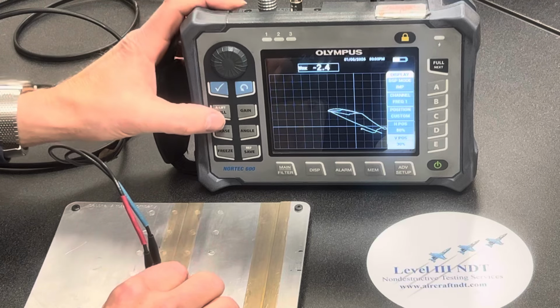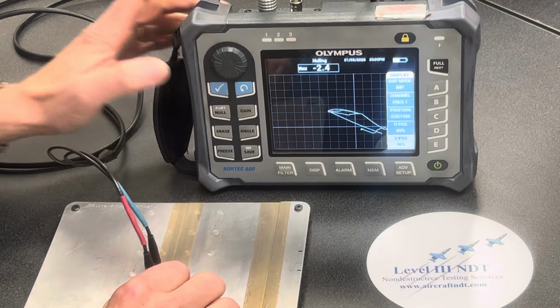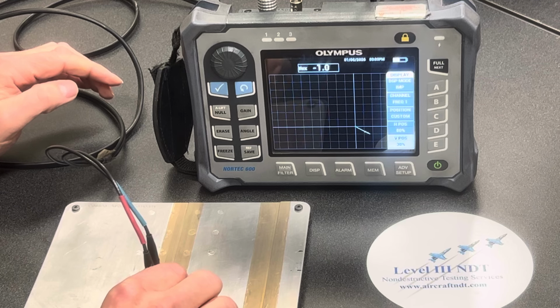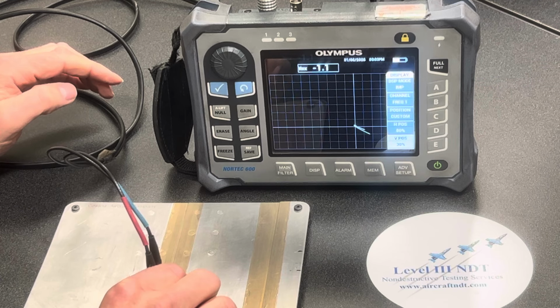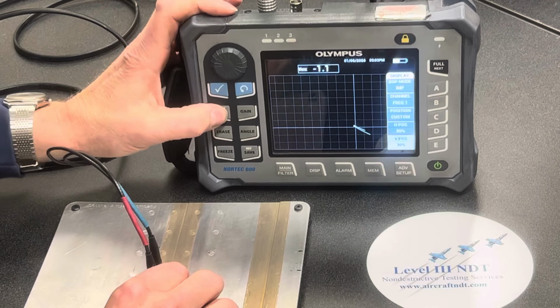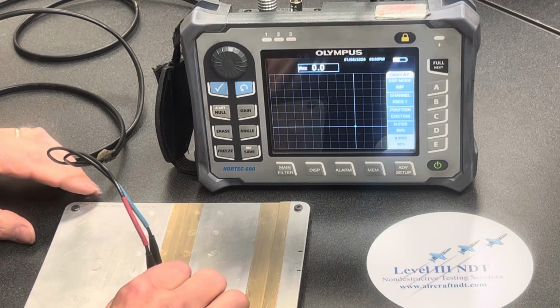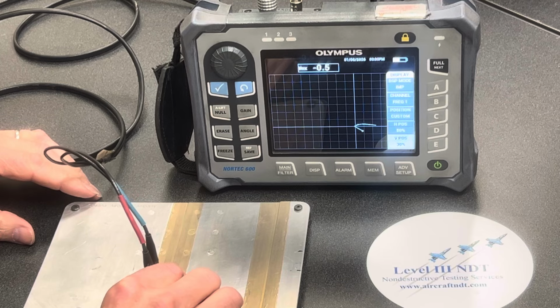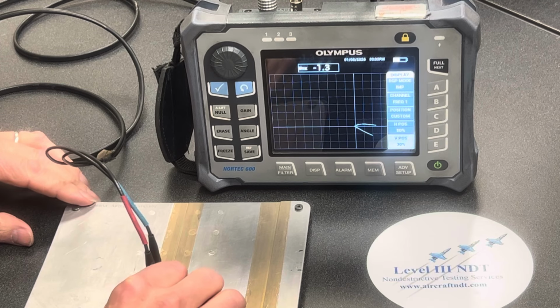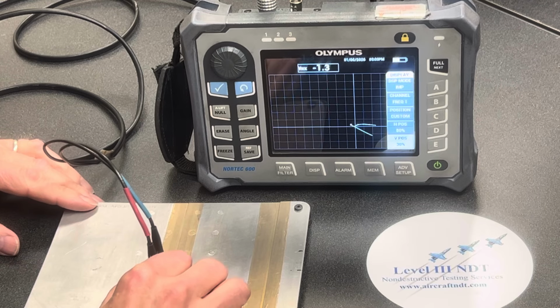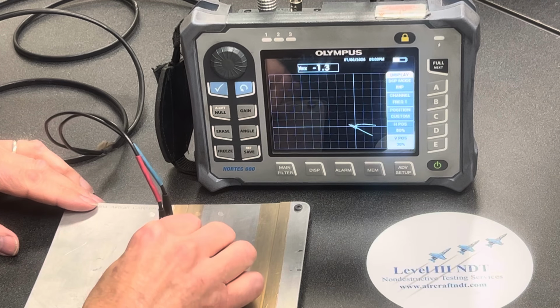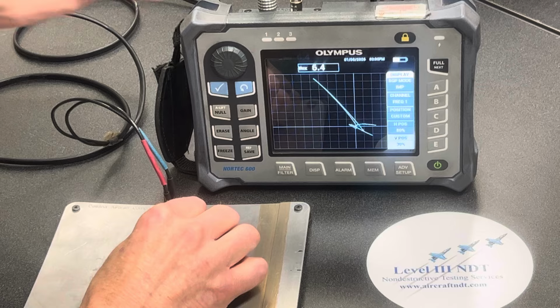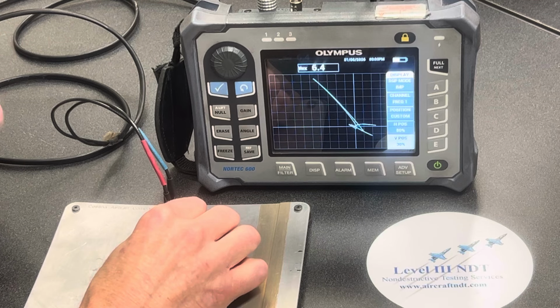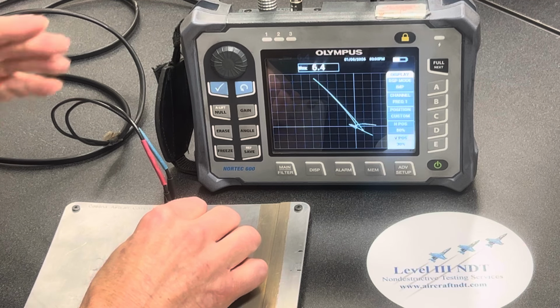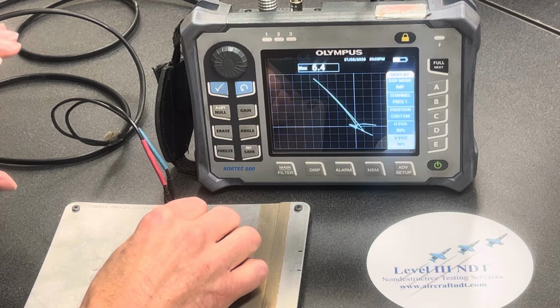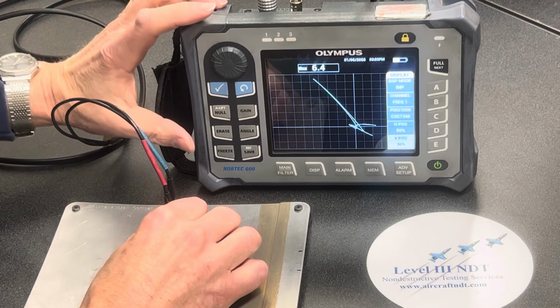Now, when we null the probe on the material, again, we're going to find the maximum point, and that should be right at our null point at 80 and 30. Check our liftoff again, it goes to the right, it goes down and to the right, and then we'll slide over our simulated crack. We want at least 6 vertical divisions. So we're just above that, so that's pretty much a very good calibration.